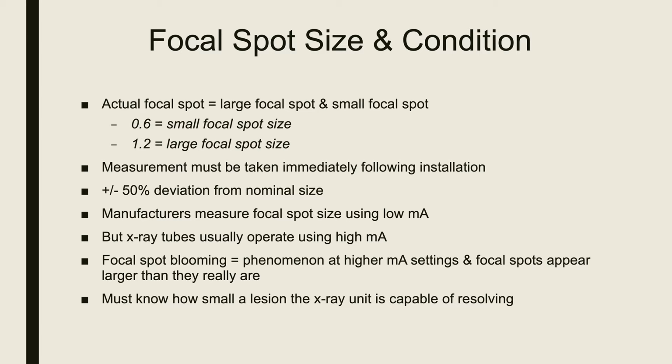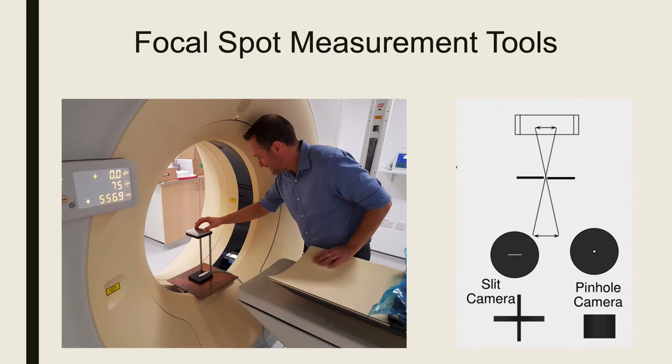And this is just showing you what the test looks like. This is somebody who's setting the focal spot test up in a CT scanner. There's a slit camera or a pinhole camera, but they're both doing the same thing.